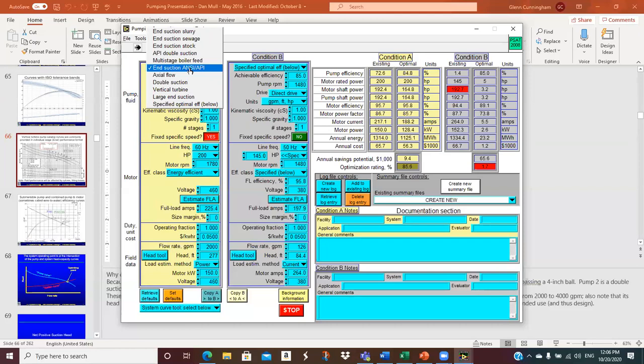End suction is the one we typically default to. That's probably the most common type of pump. We've got axial flow. Double suction would be larger than the end suction. Vertical turbine: the motor sits up high, and there's a shaft that extends down into a tank, or what they call a hot well or a cold well, and you have multiple impellers on that rotating shaft. Those are called vertical turbine pumps, large end suction, and then you can also just specify an optimal efficiency.